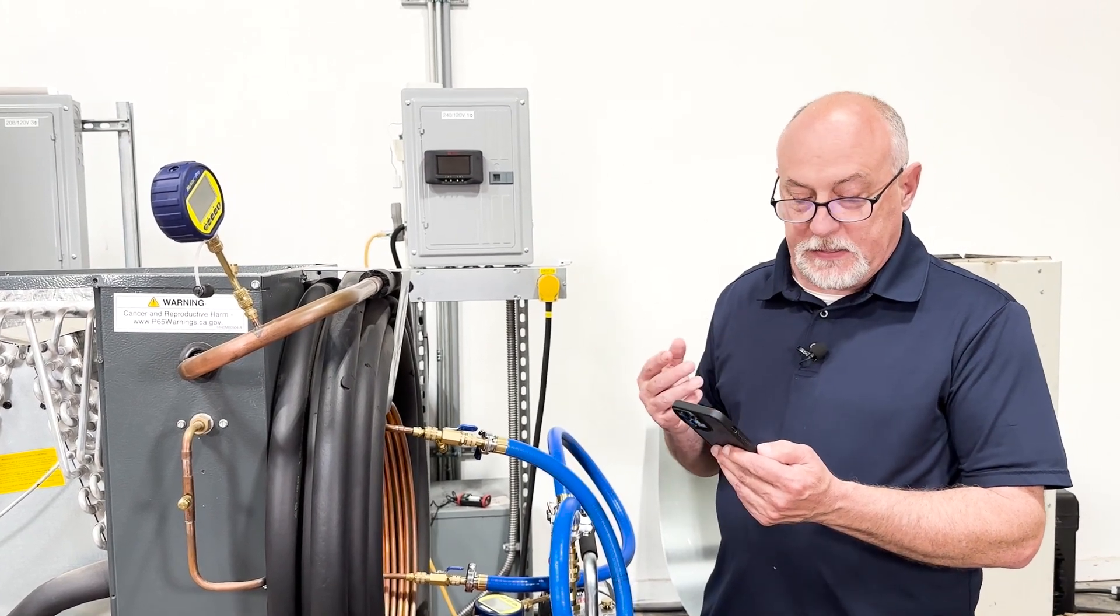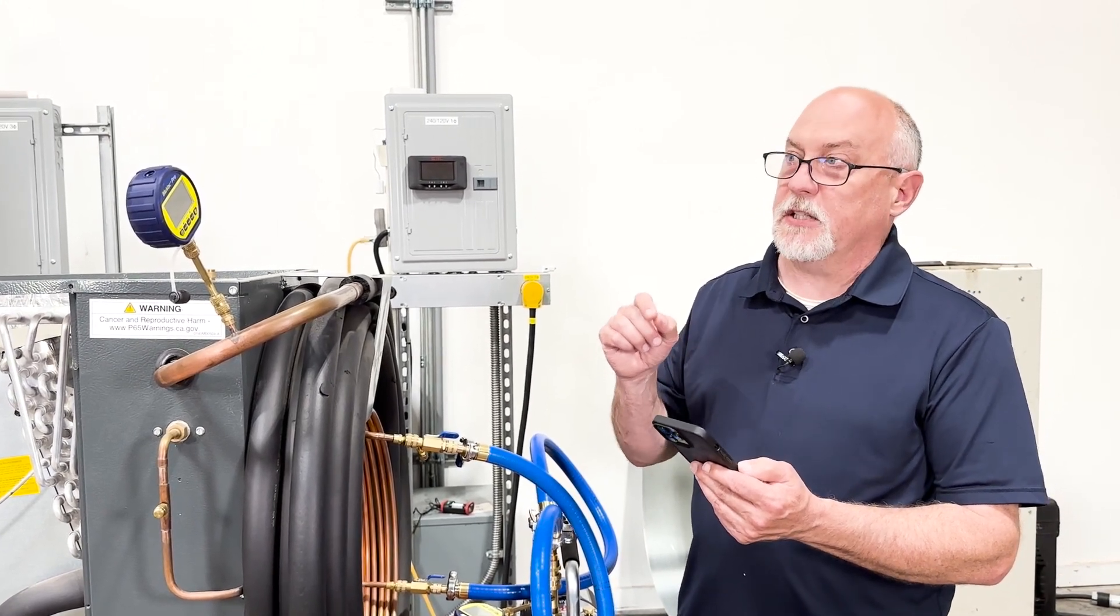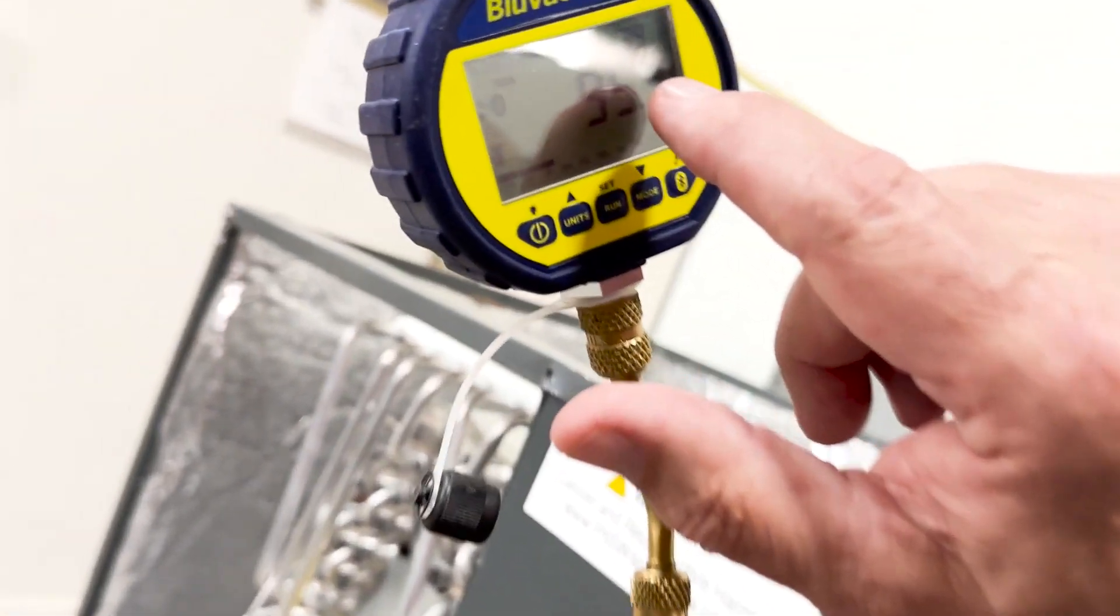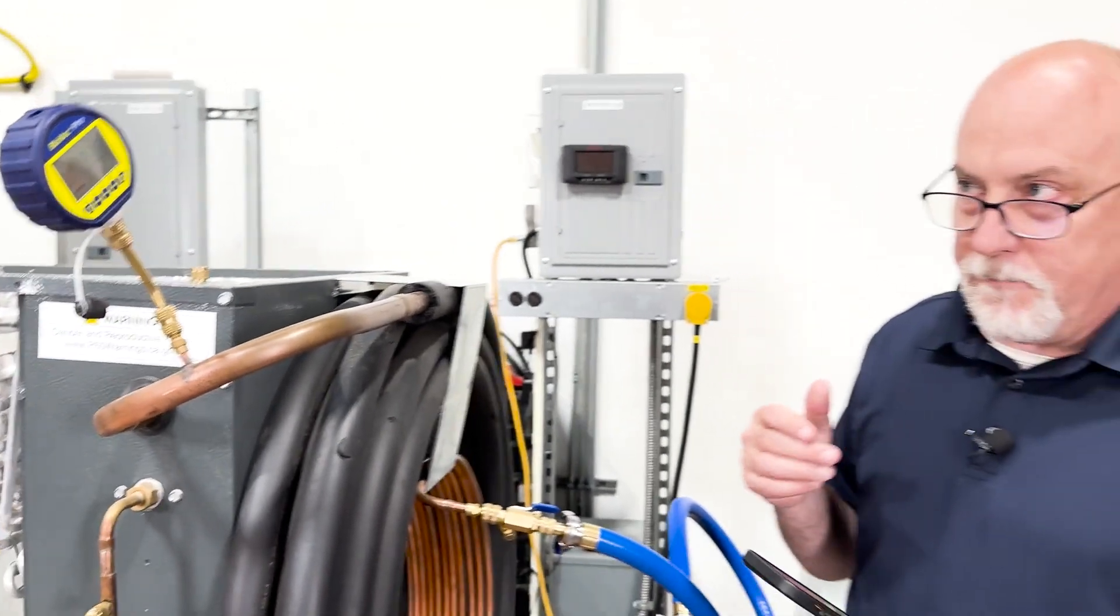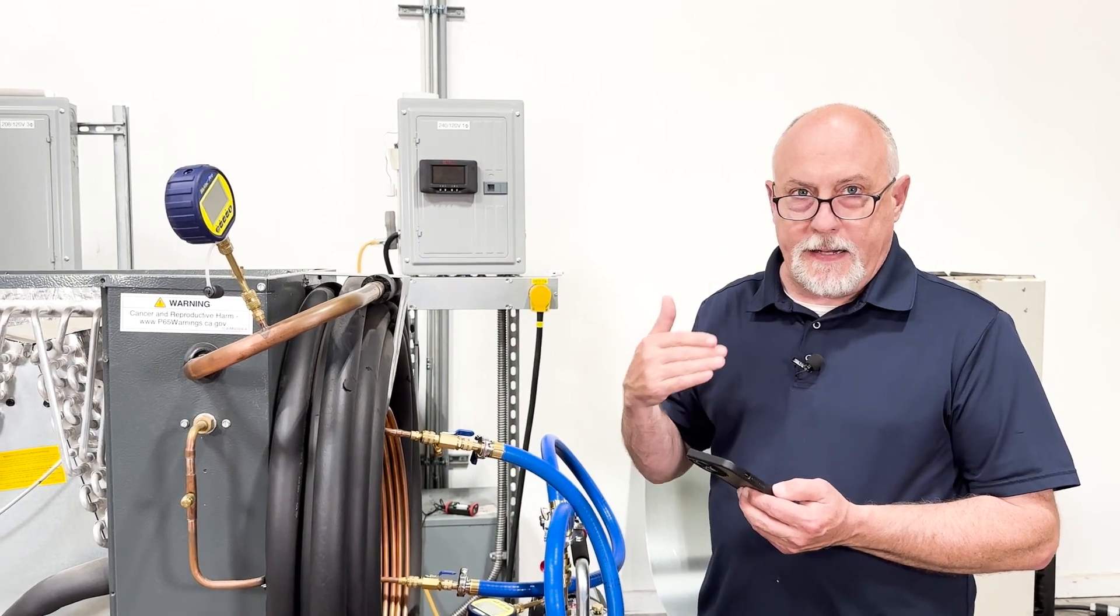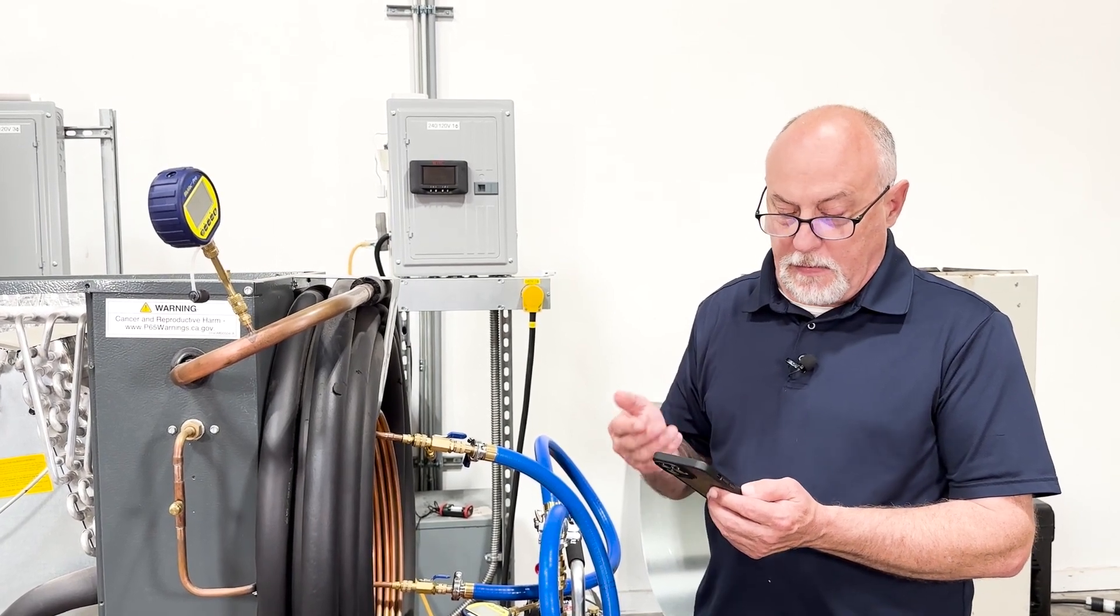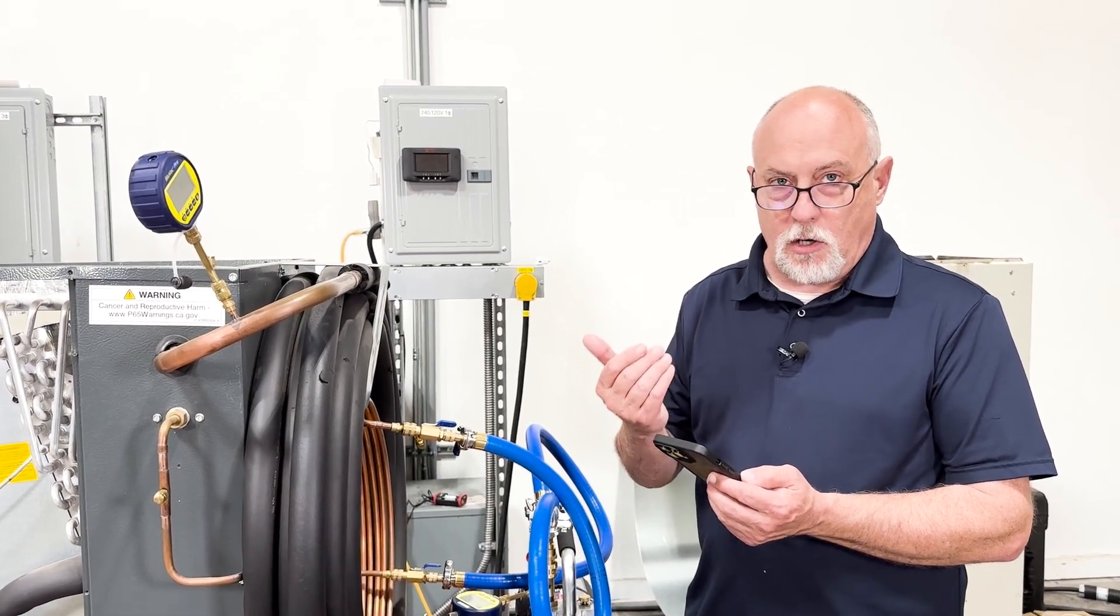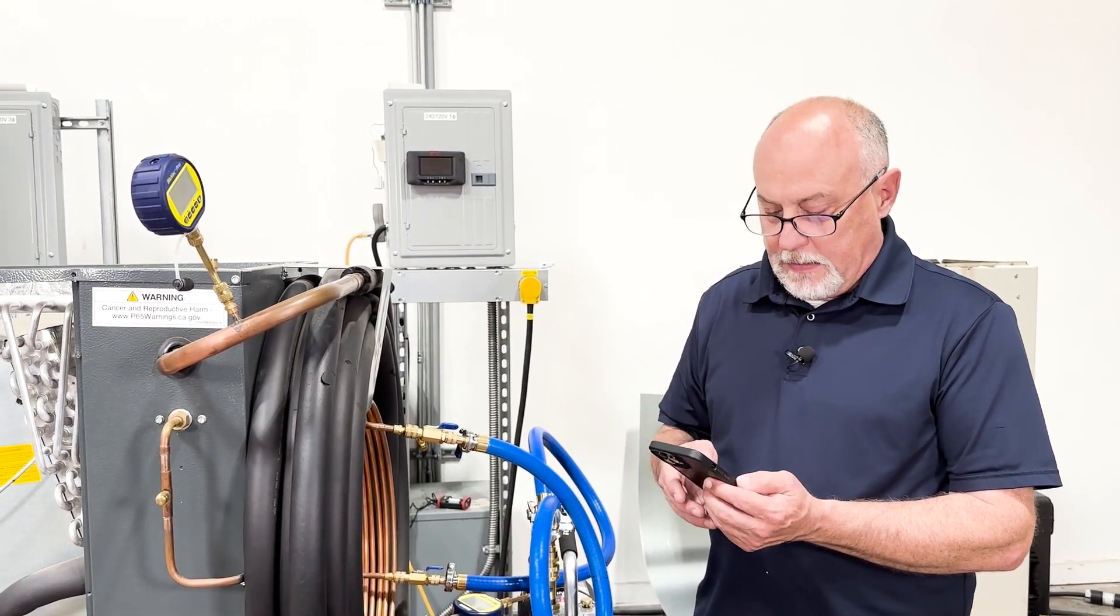All right. So now what's going to happen here is if we scroll ahead here, you're going to see we're at that four minutes that we're going to run below and start out at five minutes, but we're at our time below target. So we crossed 100 microns. That's actually started a countdown on the gauge. And that's also running here on the gauge right now. So you can see we're at 439, there we go, 436, 438, 439. We're at the same thing here on the application. So it sent a command to the gauge to tell it to now wait and go down below this target. And what we're letting it do is just basically dehydrate. If you look at this app right now, if we scroll over from the graph to the round UI, we're in our final finishing vacuum. And we're just basically drying that system out, getting all the moisture out of it so that when we do a decay test, we're not going to have an appreciable amount of rise. So we're going to give this another five minutes here and we'll come back again.